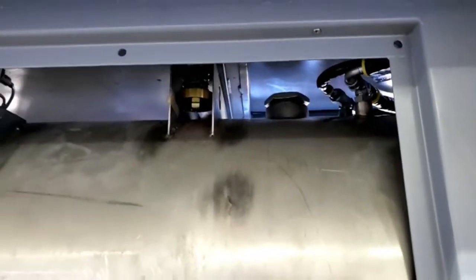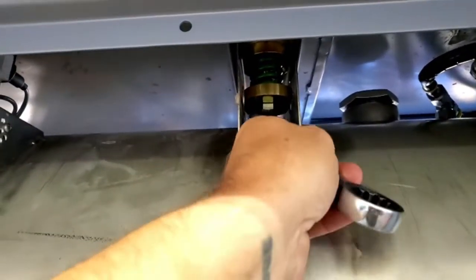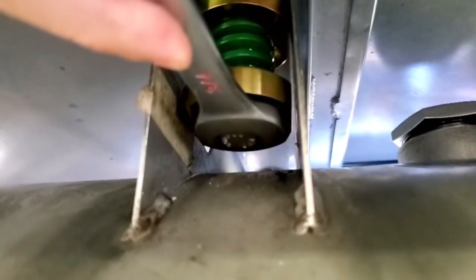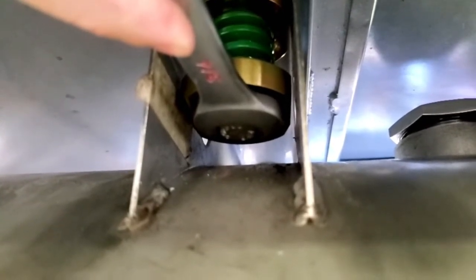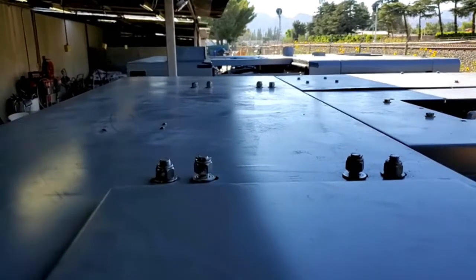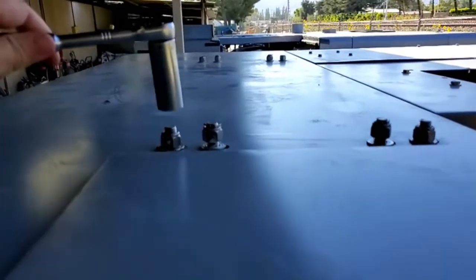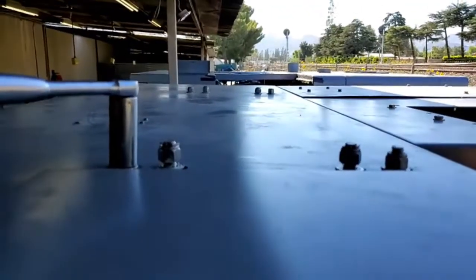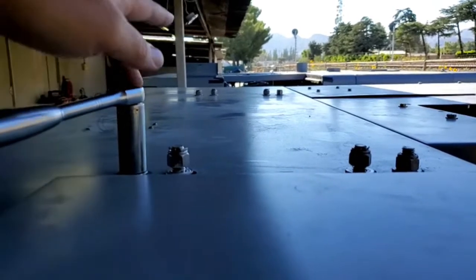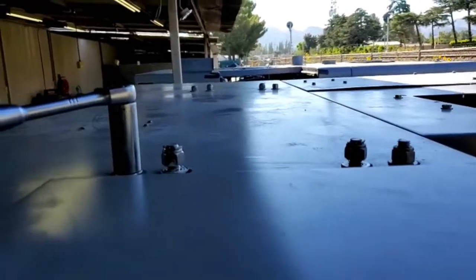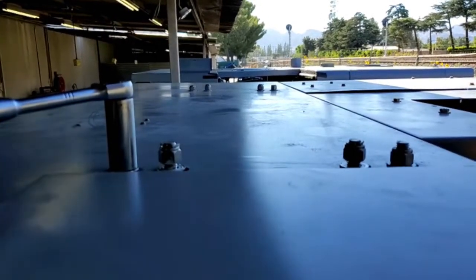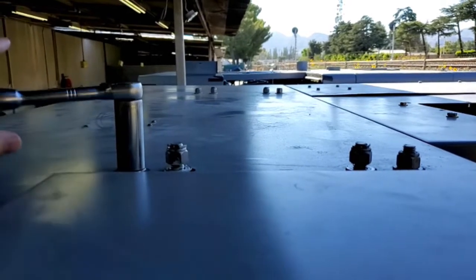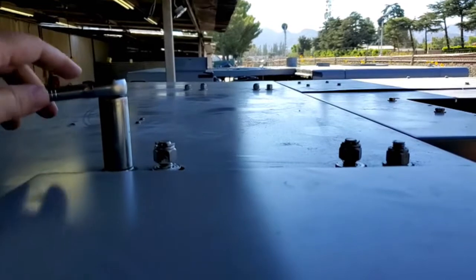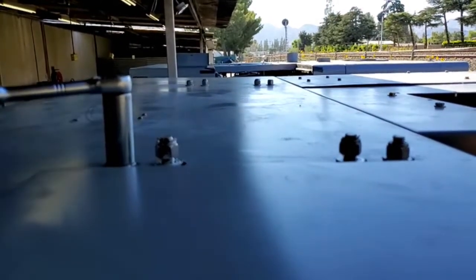Remove this panel here so you have access to the top of the reservoir. The 3/4 inch wrench will fit right up on here. Somebody can stand here and hold this while you ratchet from the top. Now from the top, with somebody holding a wrench on the inside, place your ratchet on the outside nuts, and you only need to adjust the 2 nuts on this side, so this one and this one. A slight turn clockwise will decrease the reservoir level on the HMI, and turning it counterclockwise will increase the reservoir level on the HMI.